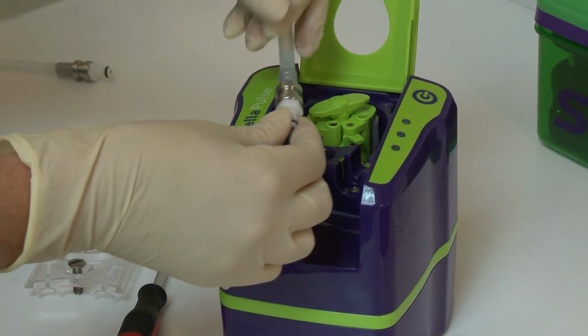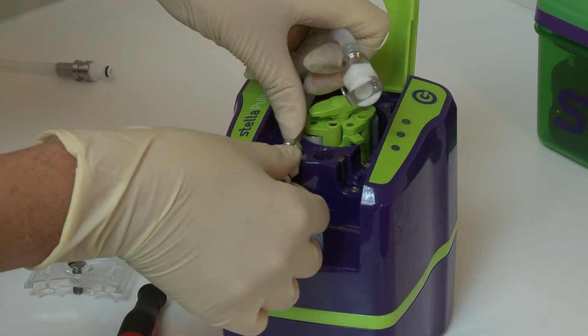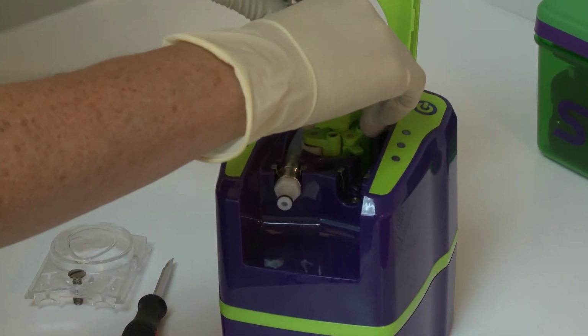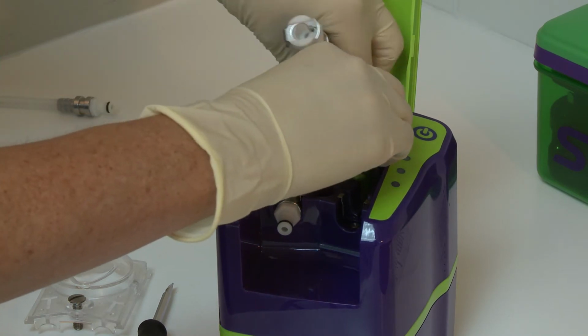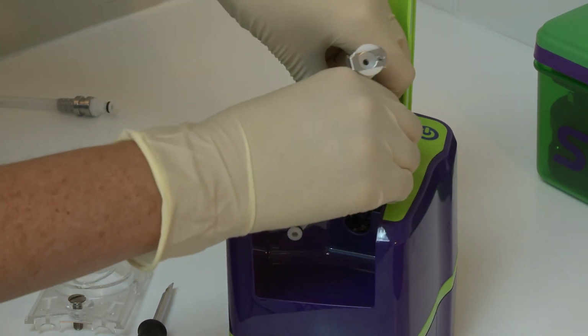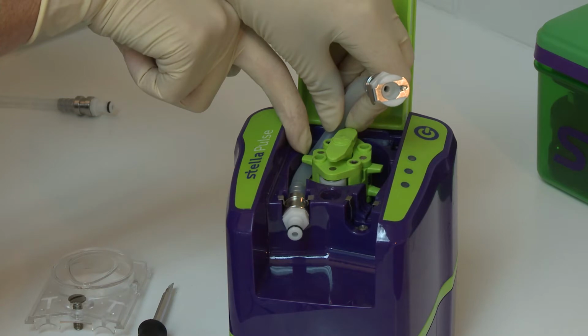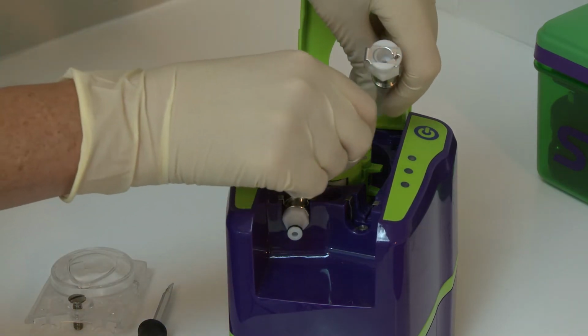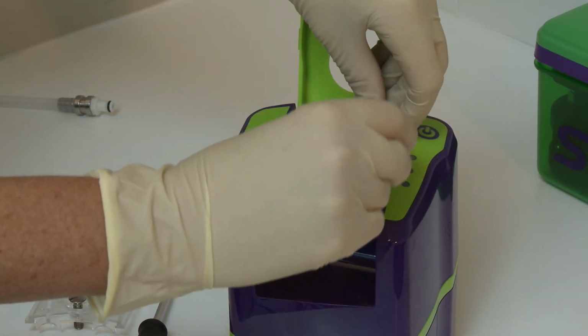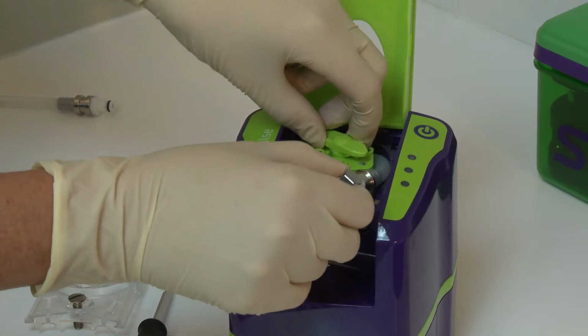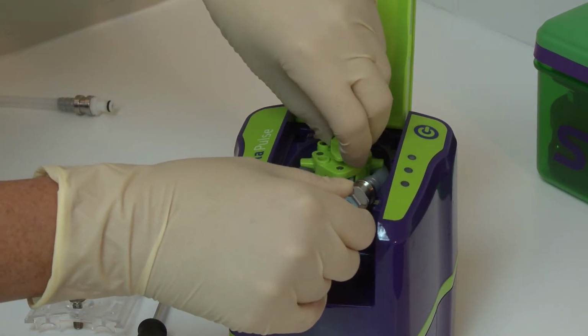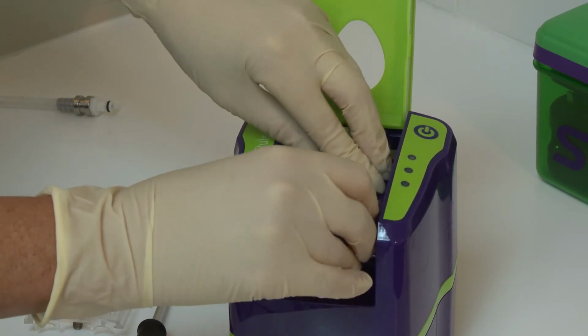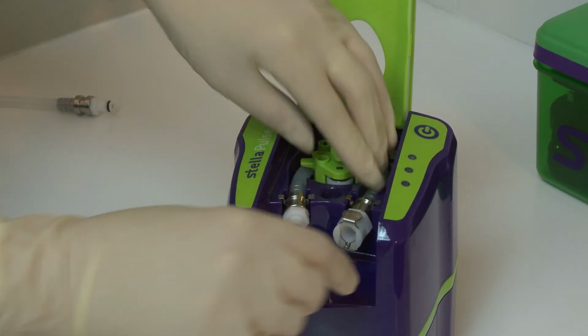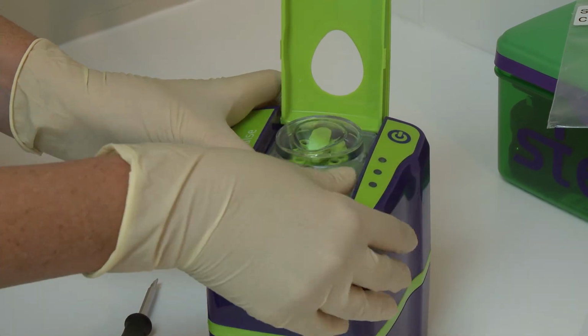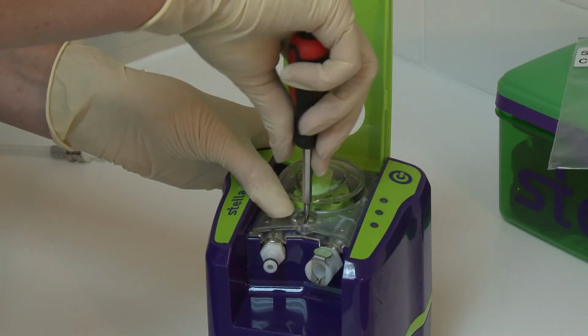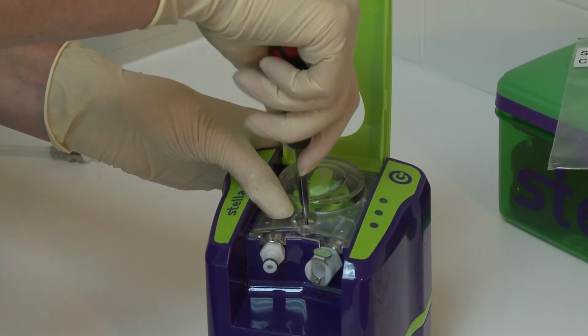4. Insert the new pump hose into Stella Pulse. Place the left-hand pump hose connector, the smaller connector with a plastic point, in first. The pump head will then guide the hose. The pump head has 2 guides that hold the pump hose central. The pump hose must sit in the middle of the guide. Lock the right-hand pump hose connector into place. Make sure that the back ridge is pushed back correctly into Stella Pulse. Fix the screws securely, taking care not to over-tighten.